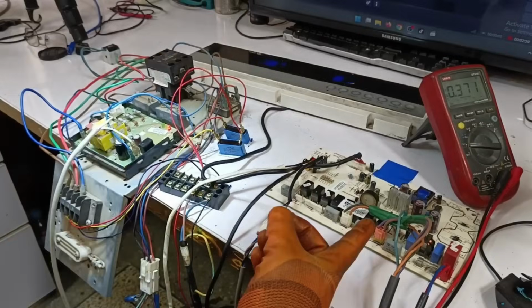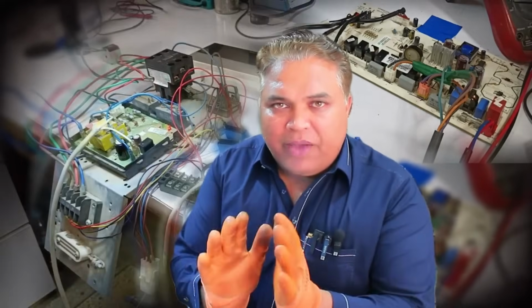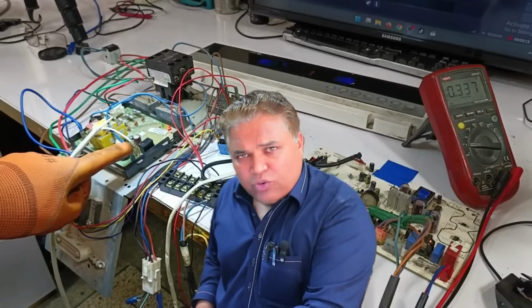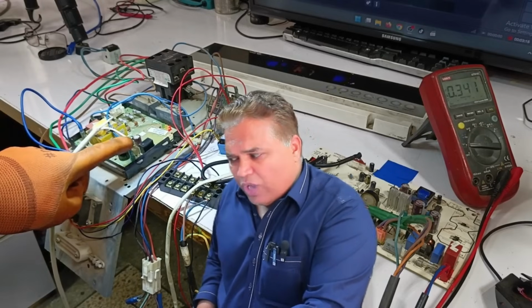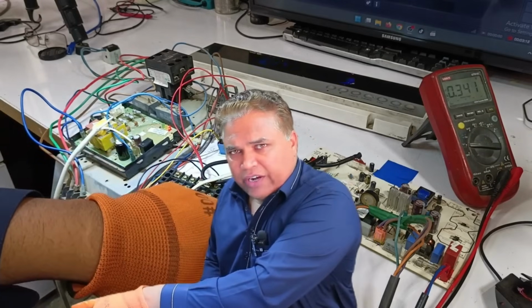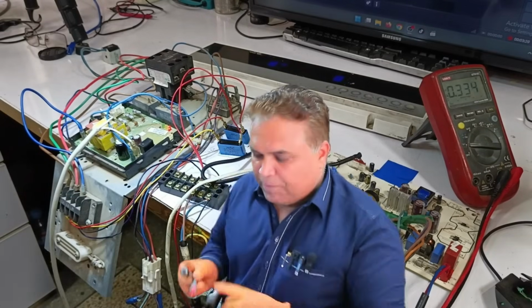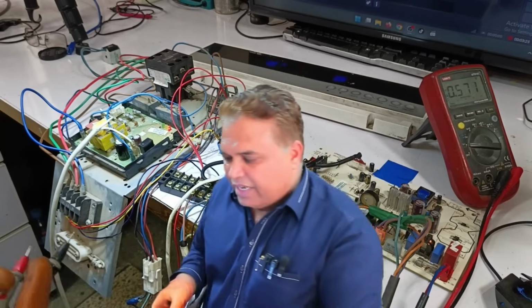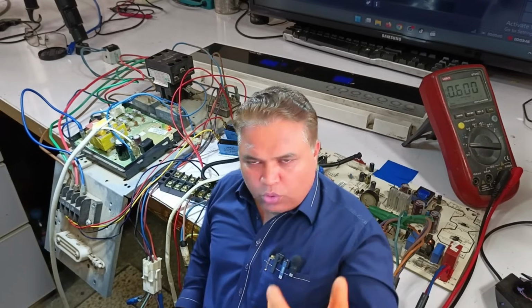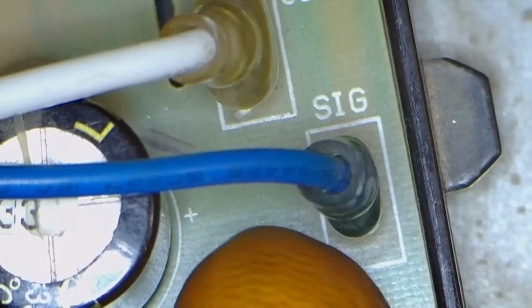After that, the PCB's next task is to activate the RY1 relay. As soon as it switches on, the signal will be sent toward the indoor unit. When the indoor unit receives this signal, it will detect that there is no fault in the outdoor unit, and it will proceed to turn on the compressor. Now, my personal assumption is that the signal is not reaching the indoor unit, which is causing this problem. To verify this, we will use a multimeter. Since the relay is switching properly, and from the signal point, the neutral should be coming after the relay switches, we will now check why the signal is not reaching the indoor unit. So let's check it now.